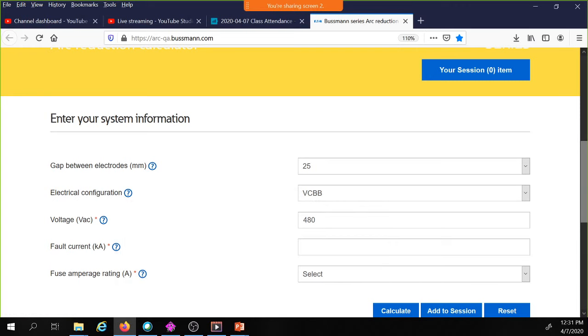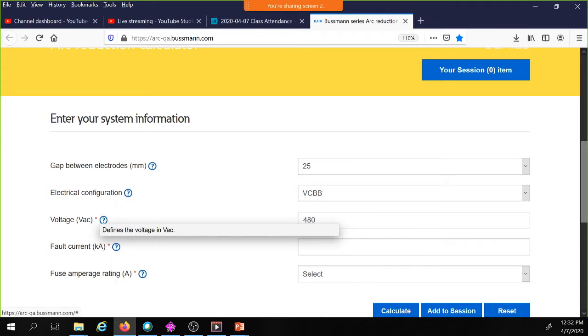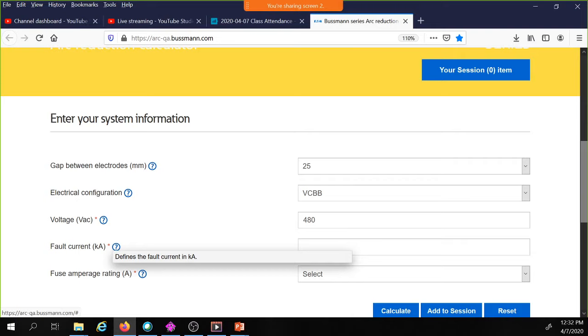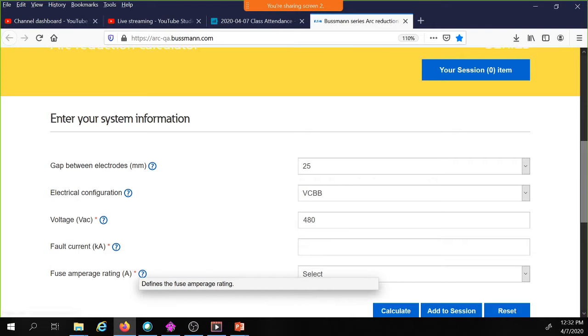This is the vertical bus, and we're going to talk a little bit more about this. You can configure VCBB, VCB, or HCB. So this gives you those parameters. This doesn't calculate incident energy. This will just calculate your arcing currents. And these are the only things that impact arcing currents: VCB, VCBB, and HCB. And we'll talk about that. This is the voltage. This is your available short circuit current. And this is your fuse size that you're going to apply this on.